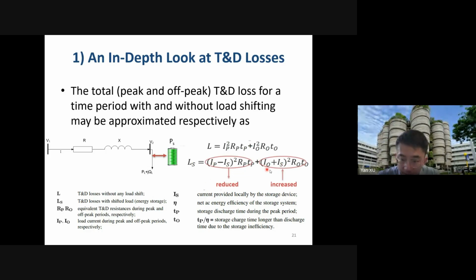You can see that this part of energy loss is reduced because we have minus IS, while this part of energy loss is increased because we have added this IS. As long as the reduced part is larger than the increased part, we can achieve the energy loss saving. That is the basic principle. This magnitude depends on IP over IO, the resistance RP and RO, as well as the period TP and TO. Note that IS is the same, so we do not reduce the total load demand, but we shift the load.